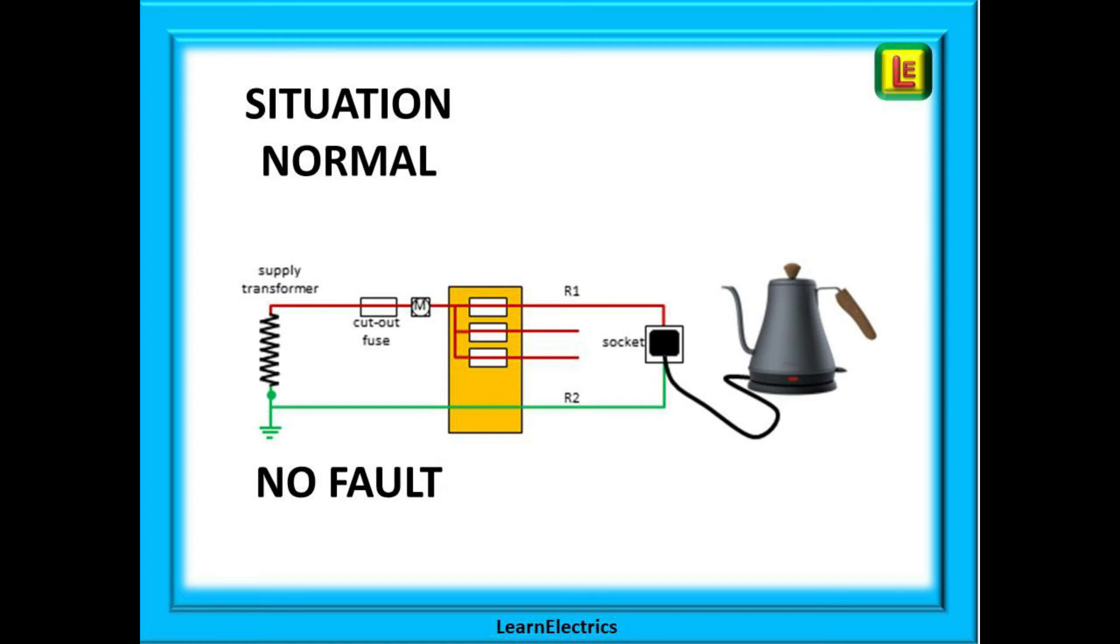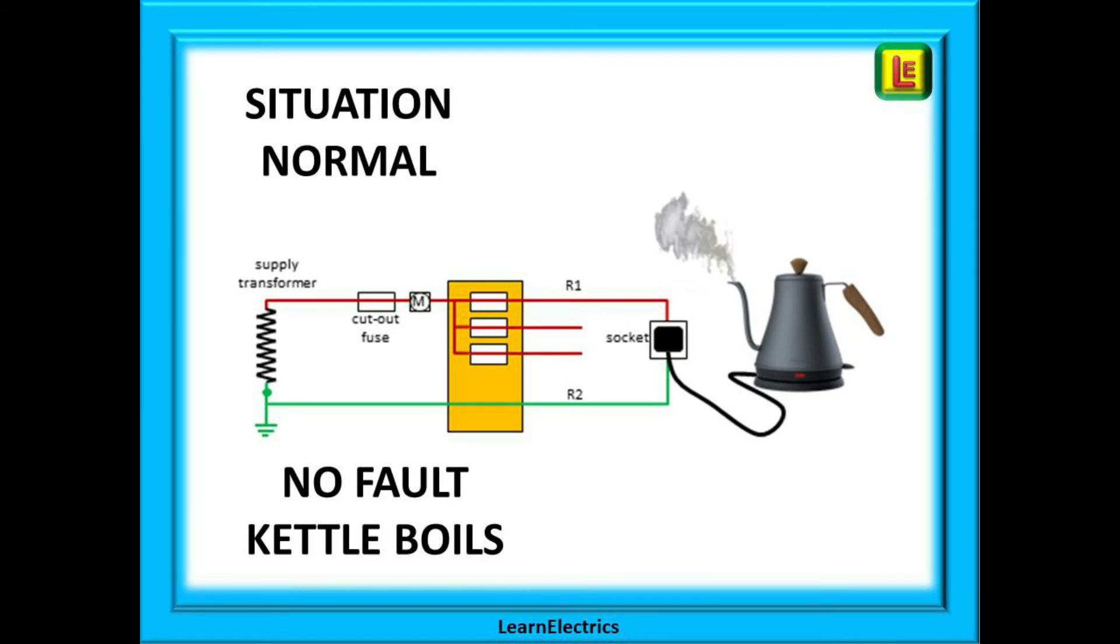Let us look then at an example. Here we have a 20 amp B type BS EN 60898 MCB that is protecting a radial socket circuit. There is no fault with the kettle that is plugged into it or with the system. We can add water to the kettle and switch it on. 10 or 12 amps flows through the kettle elements to heat the water. A short while later the kettle boils. All perfectly normal and no faults.